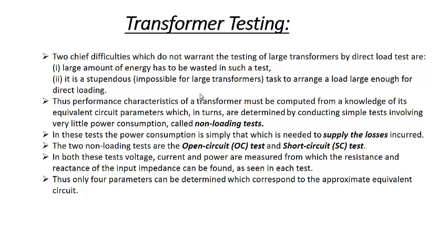Yes, in labs we may be able to load the transformer with a loading of, let's say, 1 kVA, 2 kVA or up to 5 kVA, but beyond that it's very difficult to arrange such loading. So to avoid that, we usually do the tests for the transformer which are non-loading tests.